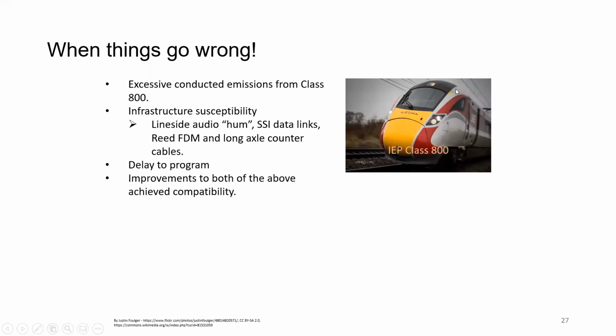This was identified only after the rolling stock was put into running service, even though it had already been tested for EMC levels. There was an integration issue related to high-speed travel of the rolling stock creating a line-side hum that affected the axle counter cables. The manufacturer was forced to redesign their circuits, especially the power accepting circuits like the pantograph, and was required to qualify for EMC testing again.